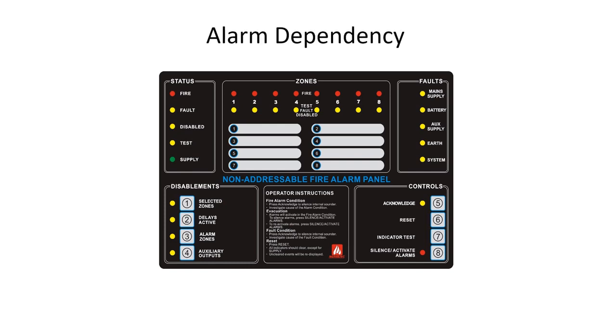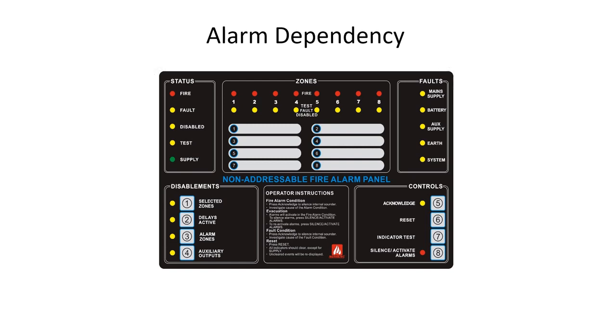To configure alarm dependency, where 2 detection zones must report an alarm before the fire alarm relay operates, enter access level 3 and press the auxiliary outputs button. The auxiliary outputs LED and acknowledge LED will flash. Press the acknowledge button to confirm. The auxiliary outputs LED will be on and the acknowledge LED will continue to flash.